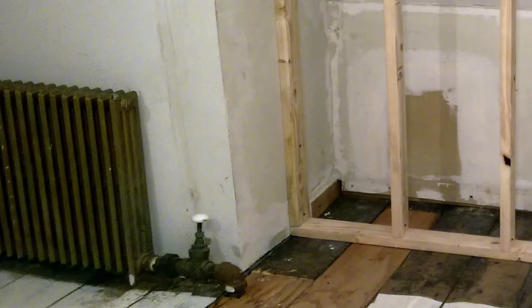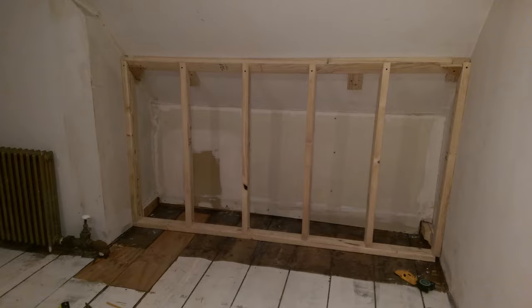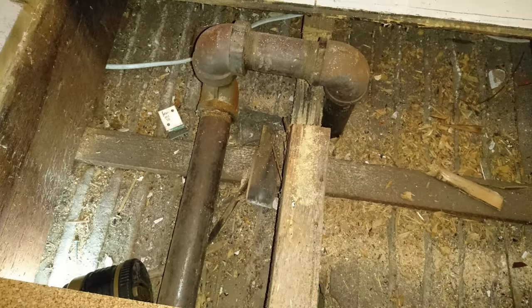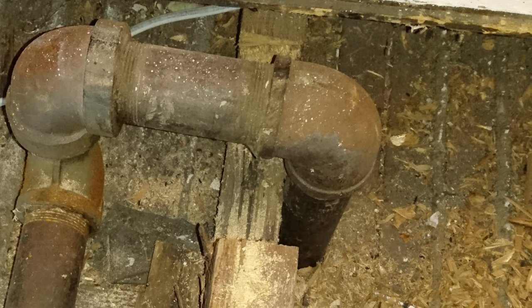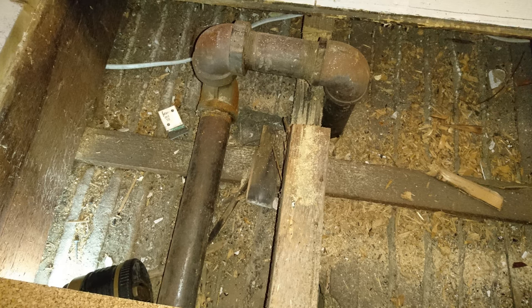Starting with patient number one, yeah, you guessed it, no heat. I could hear a gurgle and moving of water when the boiler started, but no heat. I felt around to see where the heat ended, to no avail. Since we were in construction mode, it was feasible for me to start removing the subfloor to keep doing my tracing. I wound up finding this absolute circus: a reverse U-trap paired with this piece de resistance, a floor joist hacked to pieces like it was delinquent on a loan. If you want your radiator to work once and only once, then I suppose this is how you'd go about installing the plumbing.